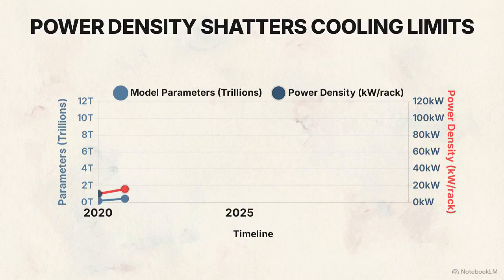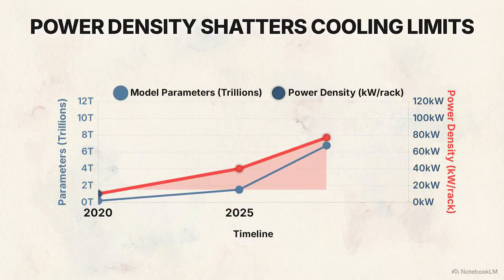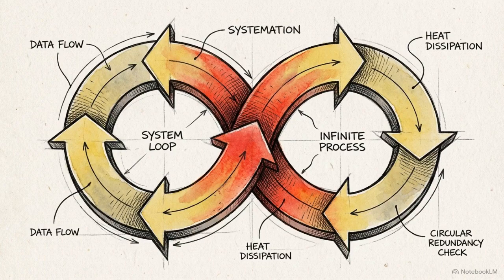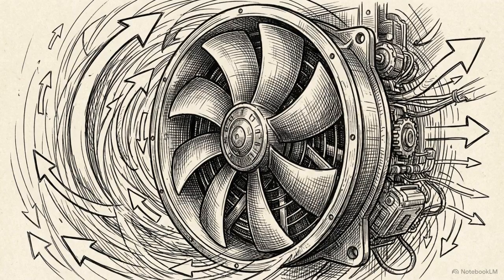As AI model sizes scale, required power density per rack skyrockets. Modern AI clusters demand 30 to 50 kilowatts per rack, with advanced setups pushing toward 100 kilowatts, completely shattering the strict physical limits of air cooling. Forcing an air-cooled system to handle these loads creates a negative feedback loop. Moving that volume of air requires hurricane-force fans. Those massive fans consume up to 15% of the server's total power, which immediately generates even more heat.